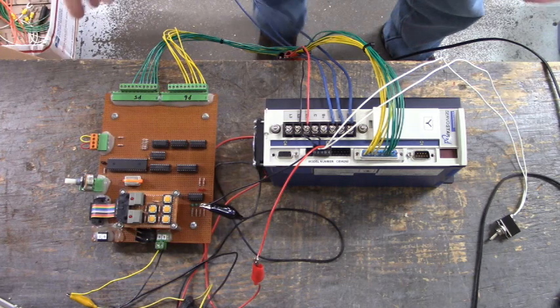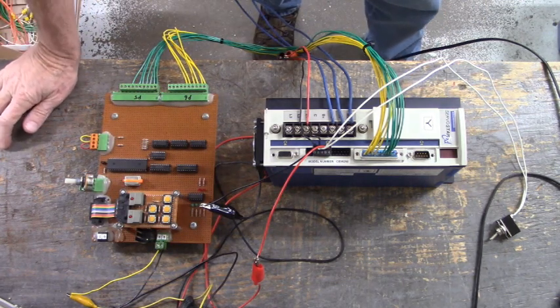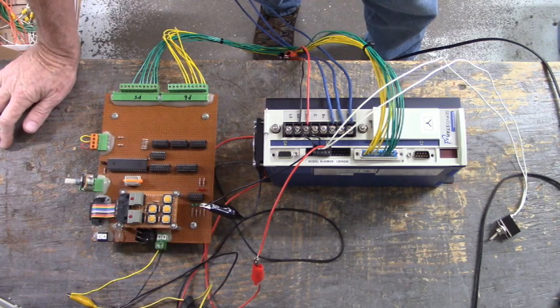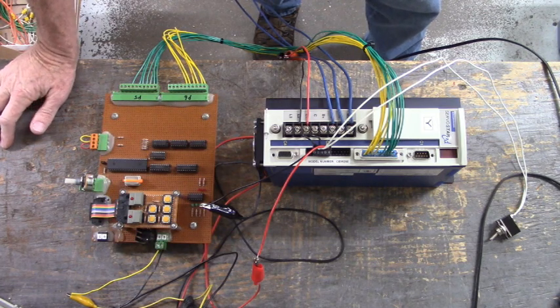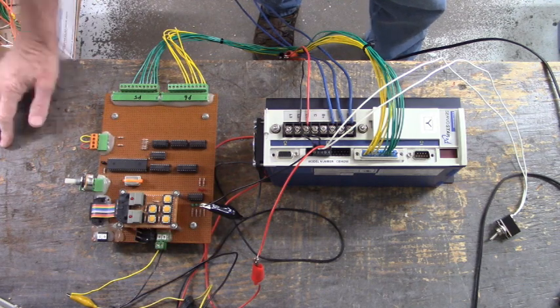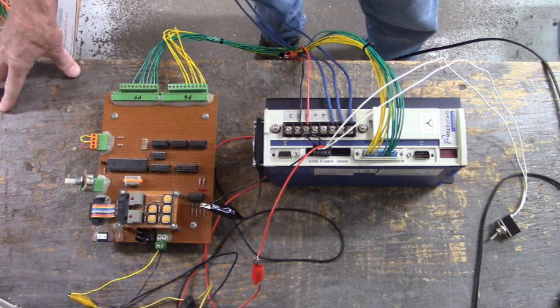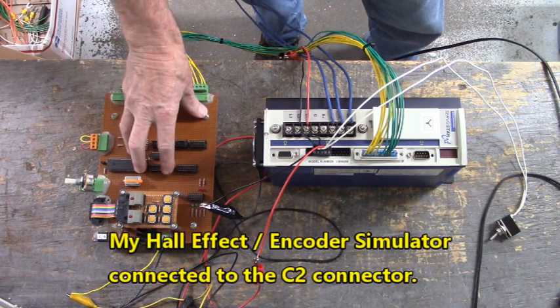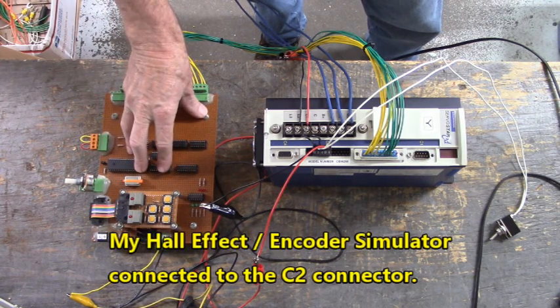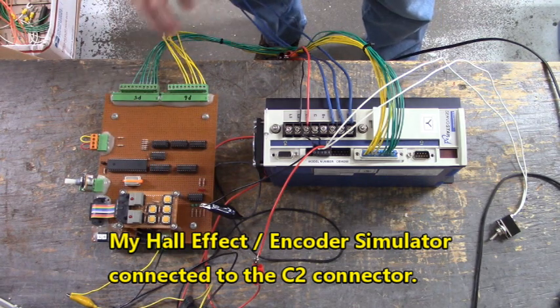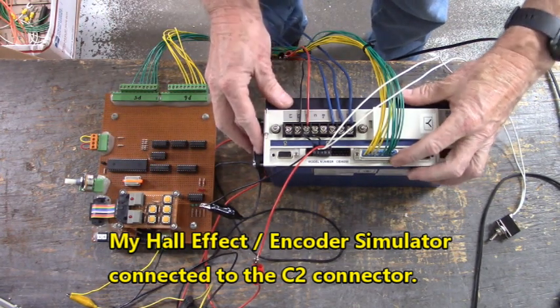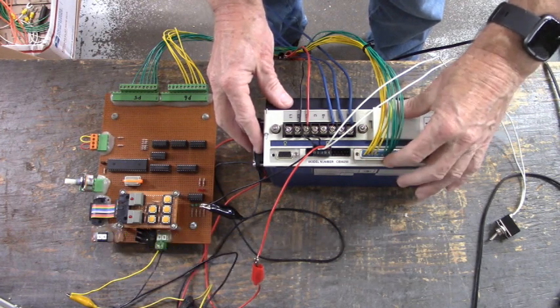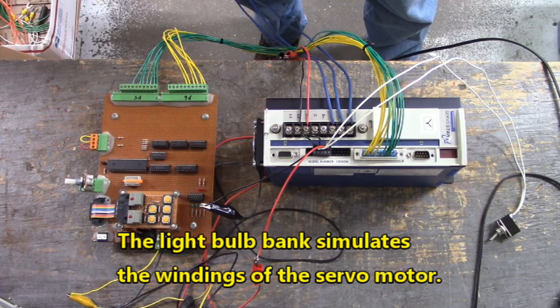Now, of course, I don't have the motor. I never have the servo motor with the drive. I'll either have the servo drive with no servo motor or a servo motor with no servo drive. And if I do get both at the same time, I don't have the cables to connect them together. So I'm going to use my Hall Effect incremental encoder simulator going to the C2 connector, the DB25 connector. And I'm going to use the light bulb bank to simulate the servo motor.